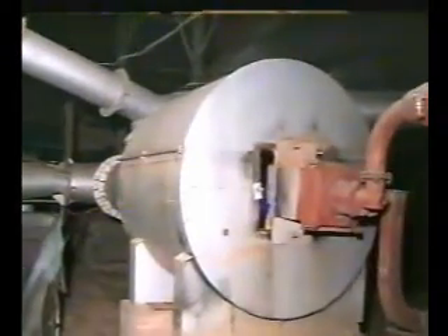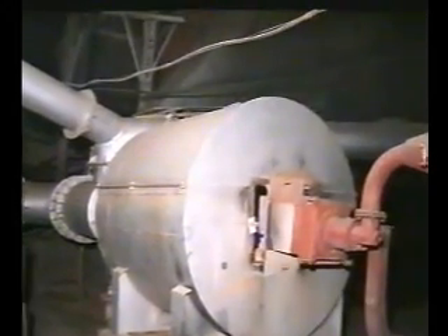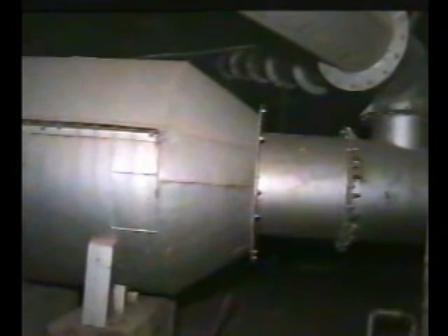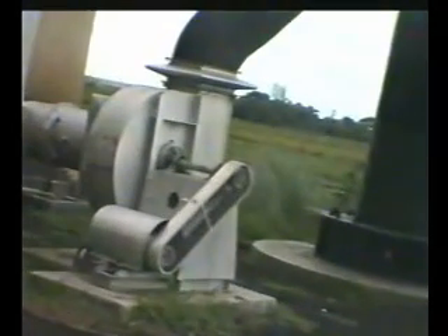Finally, here we see producer gas used for the mechanical dryer. Gas is being fired in this refractory lined vessel to get a flue gas at about 1000 degrees centigrade. The stack from the boiler at about 200 degrees centigrade is being collected through this pipeline, and the exhaust from the DG set at about 500 degrees centigrade is also made available. Now, the mixture is being diluted by ambient air to achieve the final temperature at 125 degrees centigrade. In this process, the boiler with its accessories can be eliminated to cut down huge investments. Moreover, this air is absolutely clean and particulate free.